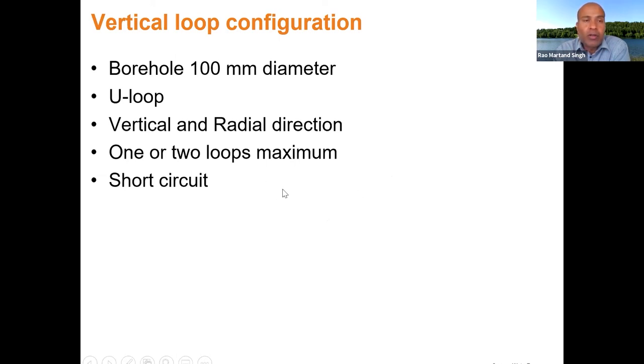Generally when you go for a vertical borehole, it is used with one loop. Sometimes two loops can be utilized, but mostly it is one loop. If two loops are put in a borehole, you need to make sure there is no short circuit, so the loops should not touch each other.